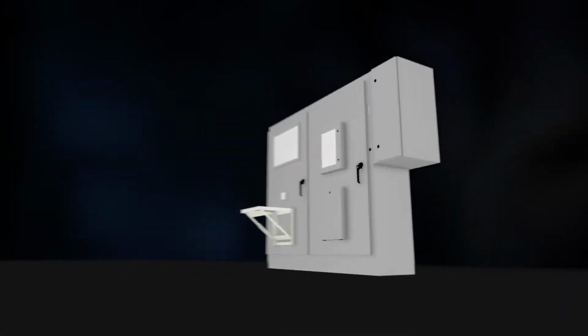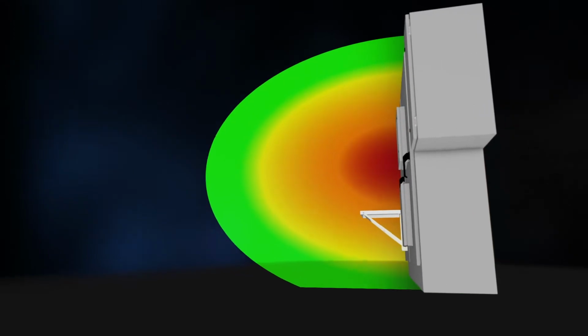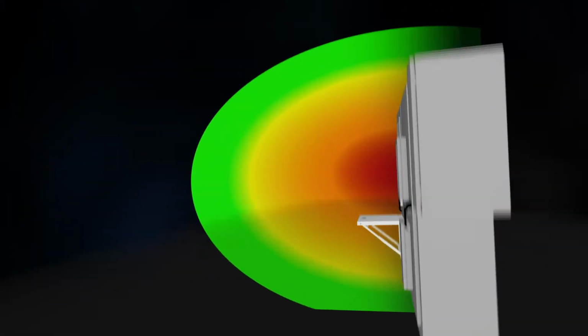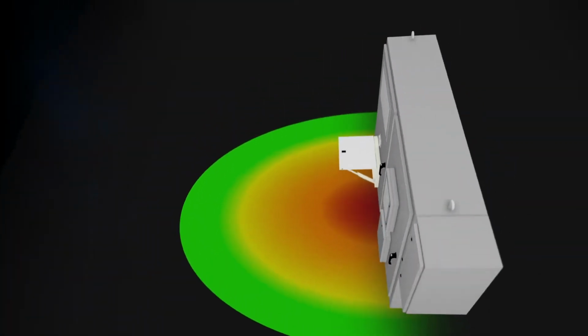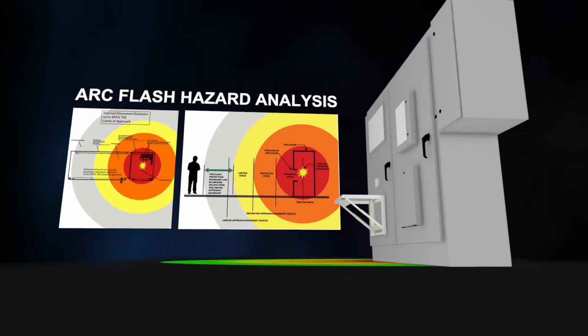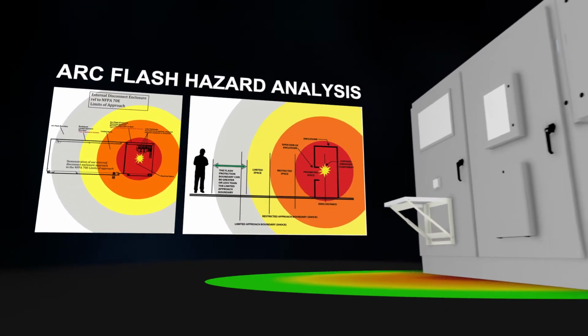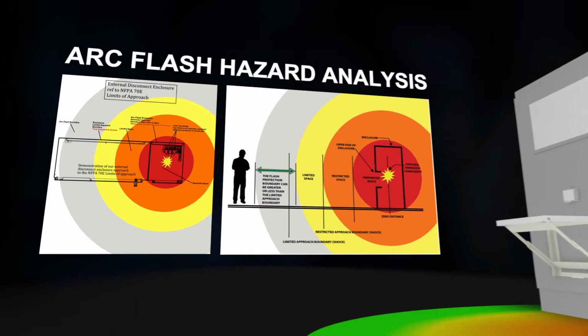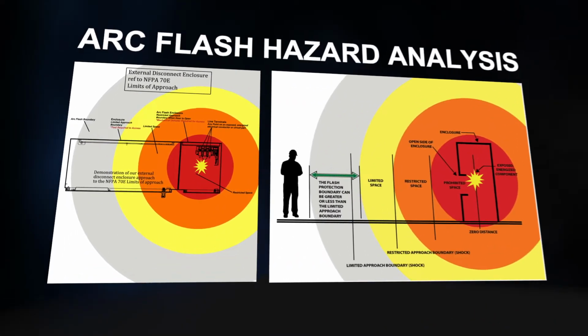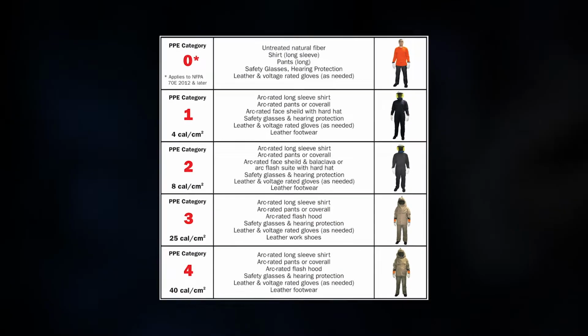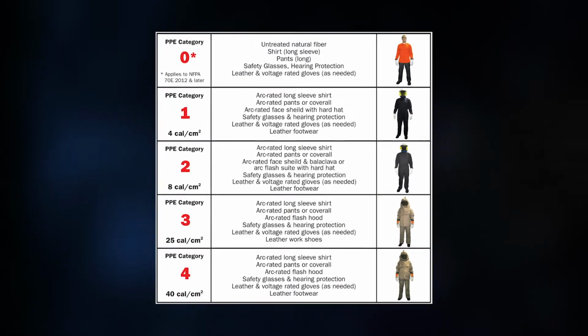First, let's talk about what's required of an electrical enclosure to meet arc flash safety requirements. This is an easy answer. Ultimately, there is nothing required. It's up to employers to determine and perform an arc flash safety hazard analysis to determine incident energy and boundaries, then establish the level of PPE, personal protection equipment, required when accessing the enclosure.